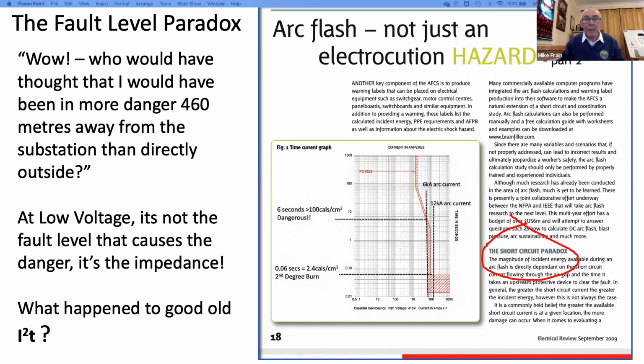So what happened to good old I²T then? Well, nothing has happened really. What I've demonstrated so far is that it depends upon the current and the time. So it happens at low voltage arcing current is less than prospective fault current anyway, which will increase the disconnection time. So with a bit less I, but a lot more T, there will be a dramatic increase in energy let through.